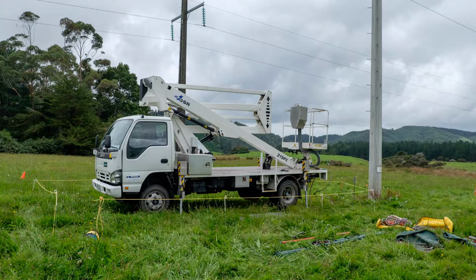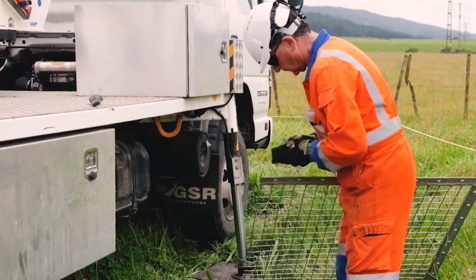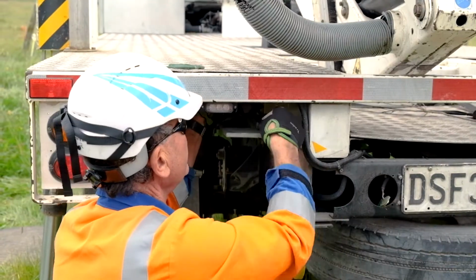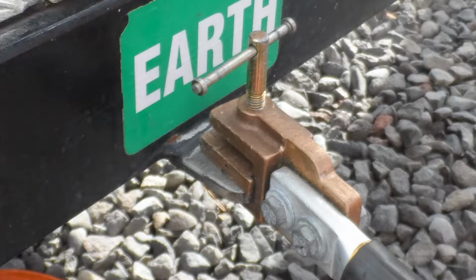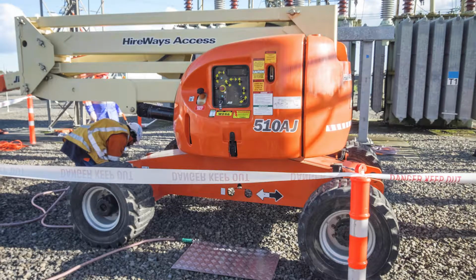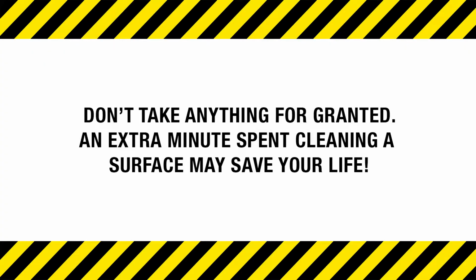Dedicated earthing points on mobile plant need the same cleaning as galvanized steel. Make sure that the earthing plates on all your mobile plant are free of corrosion and, more importantly, paint, especially equipment that has been hired. Don't take anything for granted. An extra minute spent cleaning a surface may save your life.